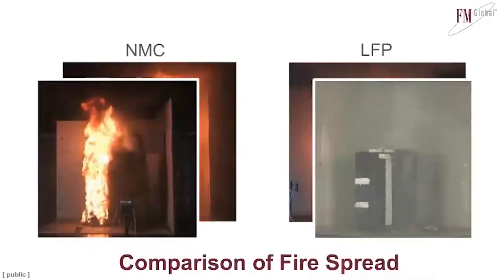Probably a bigger difference is what happens with fire spread. In the NMC system, the fire did spread from the main rack to the target rack. In the iron phosphate system, the fire was contained only to that main rack, and in fact this fire only operated one sprinkler, whereas the NMC test operated sprinklers that had a demand area that would have been over 2,500 square feet, which is kind of a standard number in some of our codes. So there really are differences in the hazard.